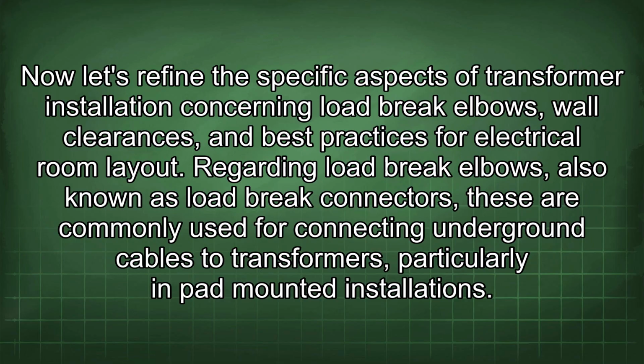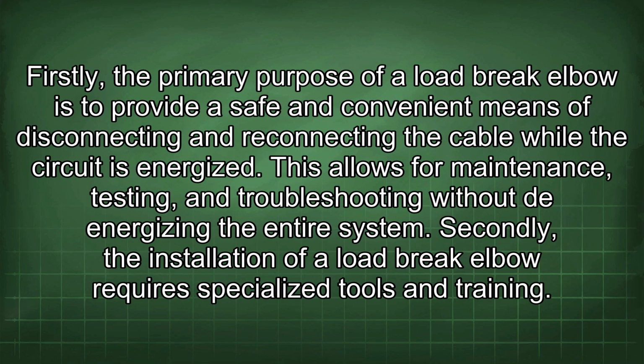Now let's refine the specific aspects of transformer installation concerning load break elbows, wall clearances, and best practices for electrical room layout. Regarding load break elbows, also known as load break connectors, these are commonly used for connecting underground cables to transformers, particularly in pad-mounted installations. Firstly, the primary purpose of a load break elbow is to provide a safe and convenient means of disconnecting and reconnecting the cable while the circuit is energized. This allows for maintenance, testing, and troubleshooting without de-energizing the entire system.